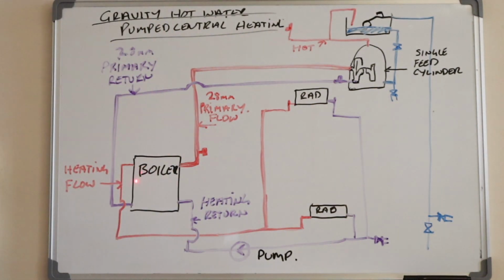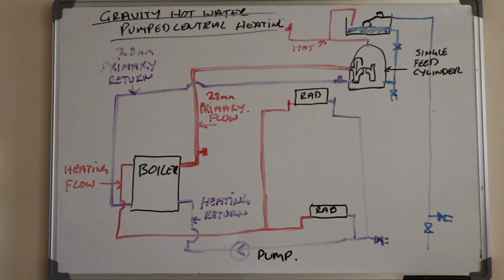So here we have the floor standing boiler. It's a floor standing balanced flue boiler, the one we're taking out. And this is the primary flow to the cylinder, and this is the primary return. And I told you they were 28mm pipe. And the reason they're 28mm pipe is because it's gravity hot water, there's no pump involved here. They need the bigger size pipe to get the flow up quickly to the cylinder.